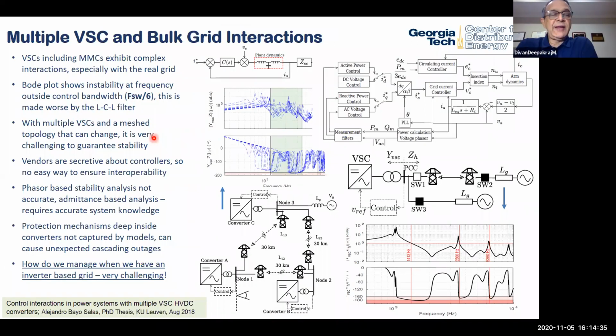So here's some examples of the issues we are beginning to see on the grid in terms of very large penetration of inverters. Large VSCs and modular multi-level converters have very complex interactions with the real grid. The switching frequencies are low, so you don't really have that level of control bandwidth. You have the LCL filter we talked about, and then we have the impedances of the system, and interactions with all the other generators and everything else.